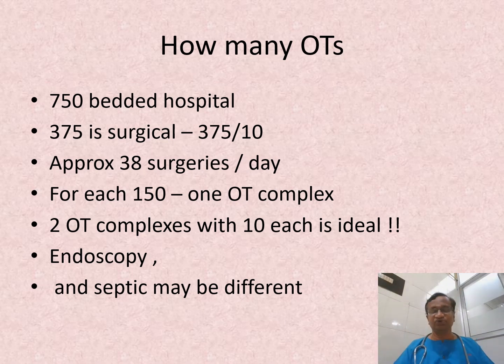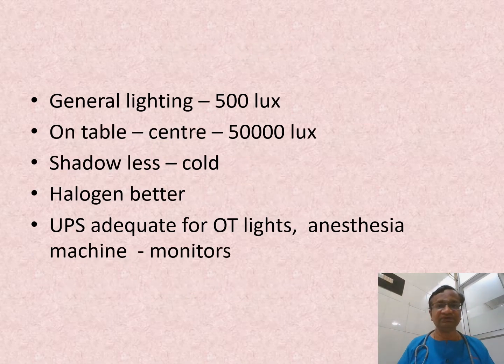If you have so many surgeries, you should have two OT complexes, and the endoscopic and septic operation theaters are different. Now, you have a 500 bedded hospital, 250, 250, 250 by 10, approximately we will do around 25 surgeries per day. So we should plan things like that.